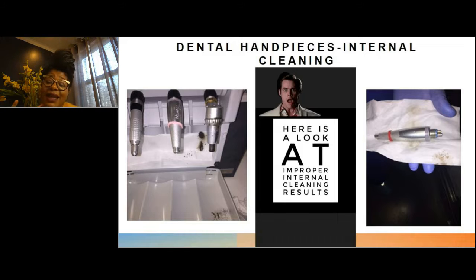What you're looking at is the IFU for this automated machine, which stated that there was a cleaning and lubricant, not chemical, it was a product that was used that would flush through the inner mechanicals of your handpiece, and it was required that the handpiece would have to go through until it expelled no discoloration. We had handpieces going into that machine and opening it up and seeing all of this sludge and buildup from reprocessing it improperly.